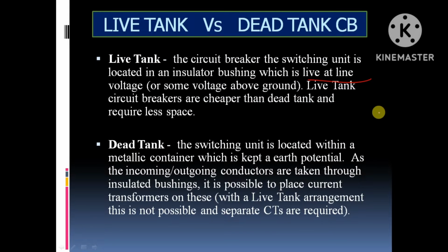Another category of breaker is called live tank and dead tank circuit breakers. Live tank means the switching unit is located in an insulator bushing which is live at the line voltage or some voltage above the ground. Whereas in dead tank circuit breakers the switching or interruption occurs within a tank at ground potential.